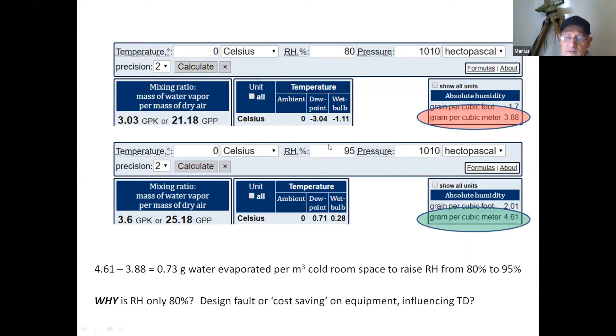and then he basically buys himself a lower relative humidity, because that cost saving inevitably gives you this problem of a lower relative humidity. And in that situation, by humidifying the air, you're addressing the humidity issue, but you're also adding moisture that's going to condense on the coil. And at these sub-zero temperatures, the coil is obviously running at colder than zero. So in that case, any condensate will freeze, and then you run into problems with defrost and you lose temperature control. So it's, for me, a very poor second choice to start humidifying air. You should have the right design that gives you the 95% without any of these fancy additions.